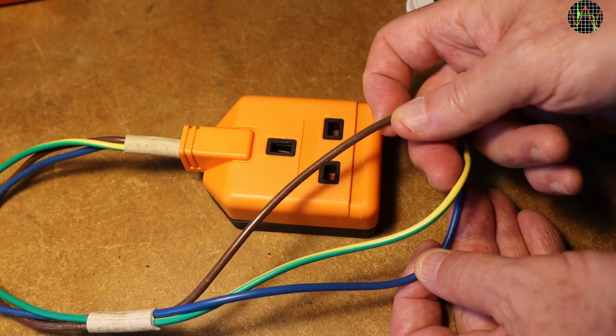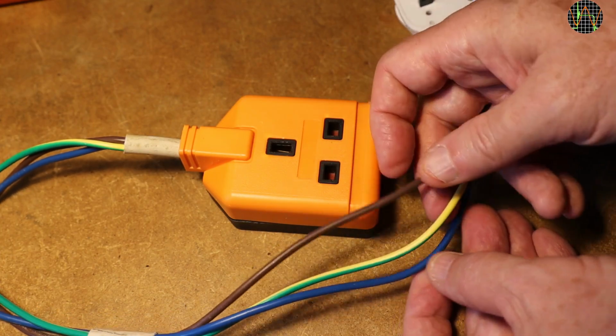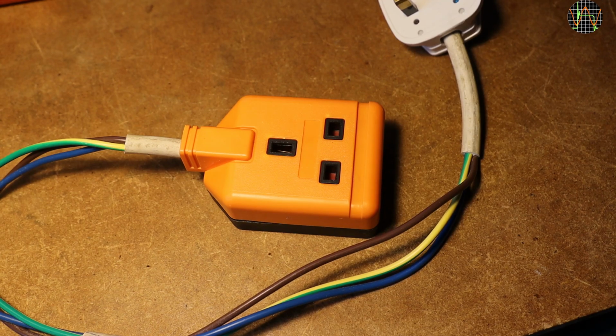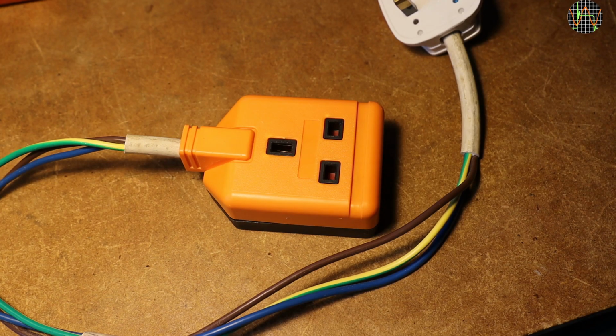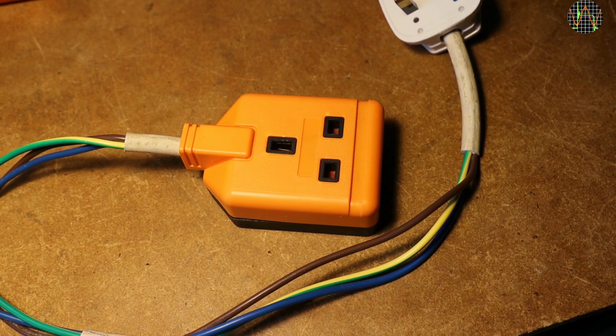The only special thing is that I removed the outer insulation to expose the three cores, so they can be clamped individually. This removal needs to be done with some care to avoid nicking the insulation of the core wires, and for the same reason the whole rig needs to be treated gently to avoid damaging the wires. Understand that if you build and use something like this, you do it at your own risk.